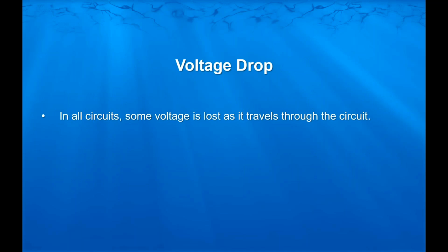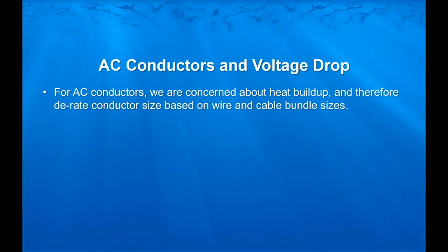Voltage drop. Voltage drop is mainly a DC issue, which we'll see. As we mentioned before, in all circuits, some voltage is lost as it travels through the circuit and is referred to simply as voltage drop. For AC conductors, we are concerned mostly about heat buildup, and that is the crux of our derating system for the conductors based on the wire itself and how many wires are bundled together.